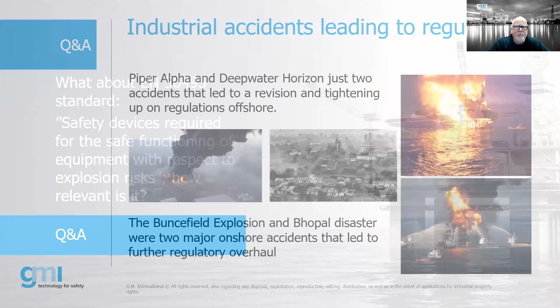This was EN 50495, right? Yeah, this actually was a question—not from this group—but we'll talk about it briefly. This is a European standard regarding safe functioning of explosion safety devices. A good example is a motor starter providing protection to an EX motor in a hazardous area. On the right-hand side you see a little motor contactor rated to protect an EX motor, marked appropriately for that application. It's been matched, if you will, to that motor. So that's where that standard comes into play. There's certification for equipment going into hazardous locations, and we also need to take into account the equipment controlling and monitoring that equipment. Be aware of that.